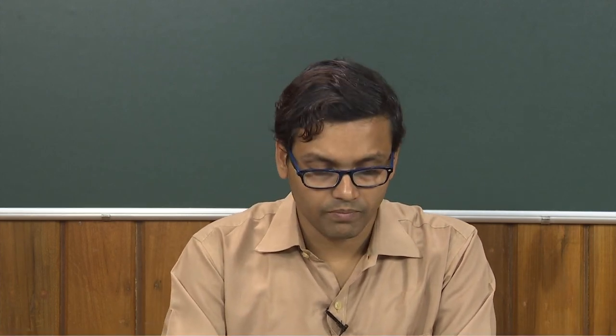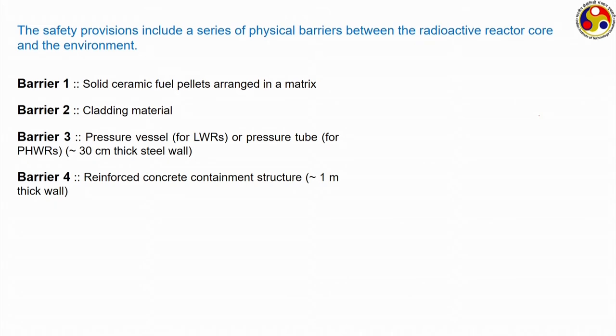The third barrier is the pressure vessel or pressure tube. Pressure vessels are pertinent to light water reactors like PWR or BWR, while PHWR uses a pressure tube type design. The walls of the pressure vessel can be very thick — conventionally around 30 centimeters of thick steel — forming the third level of barrier. Finally, the fourth barrier is the containment structure, generally made of reinforced concrete up to 1 meter thick.